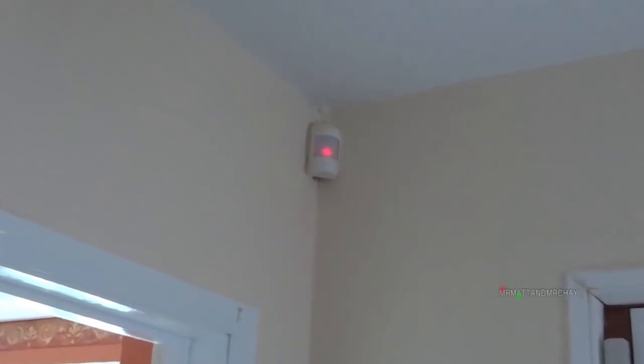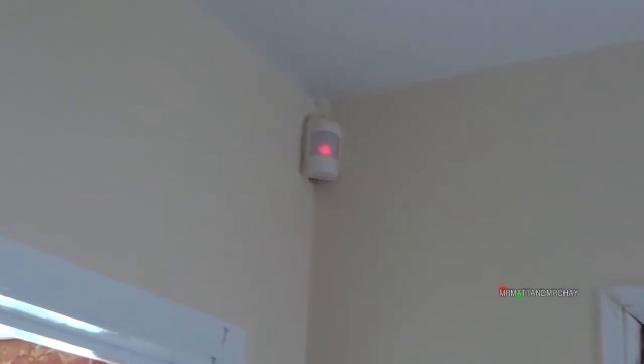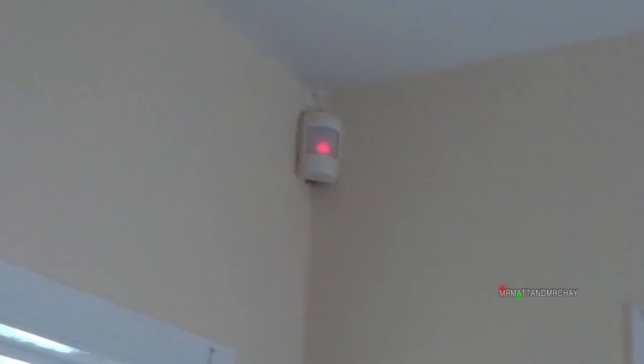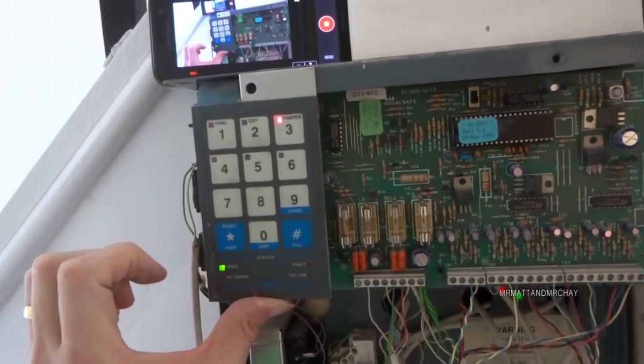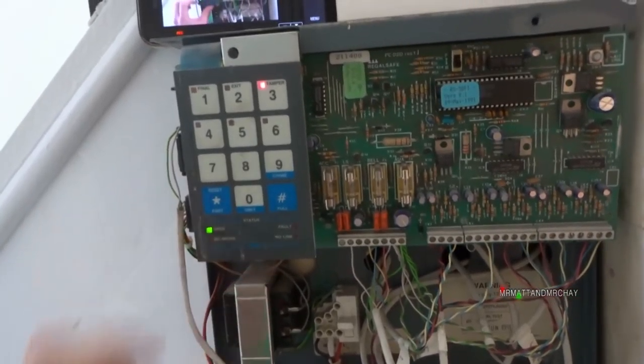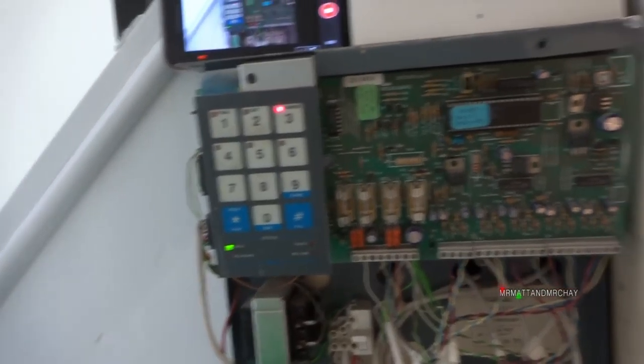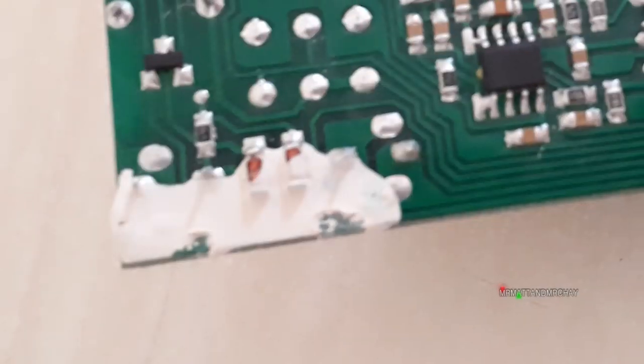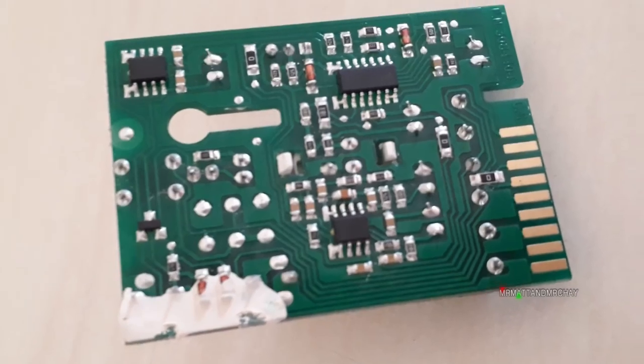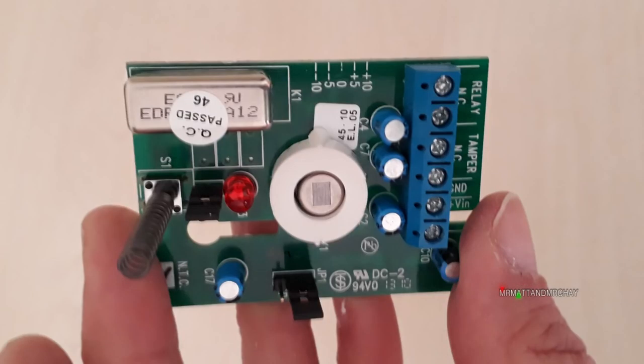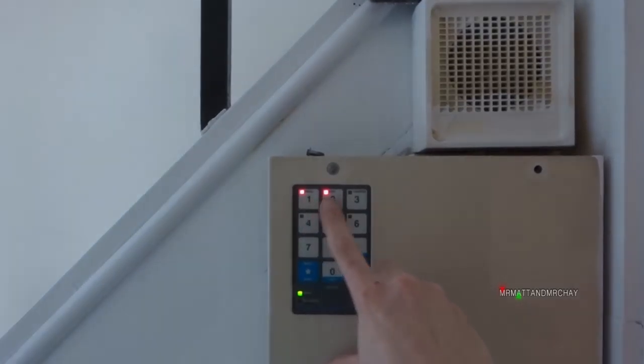The reason I'm here is the owner of the house had some painting and carpentry work done, and now the PIRs don't have any power and they cannot set the system. I found a blown auxiliary fuse, but fuses blow for a reason. So I opened up all the PIRs and found this. Somehow paint managed to get into the PIR through a fixing hole, presumably shorted out the reed relay which is on the other side. Now the paint is dry, no short circuit, and my amps test reading barely registered anything. But it was good to find a possible culprit.